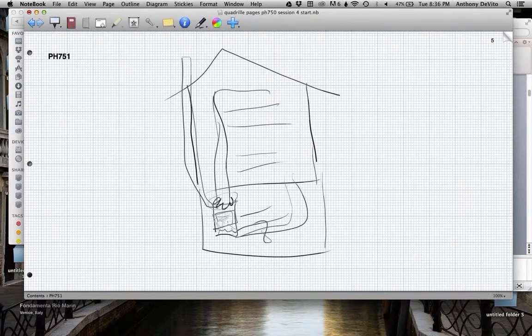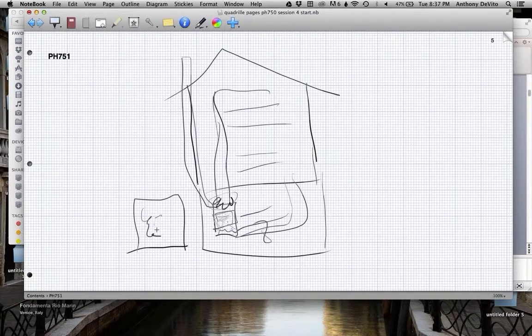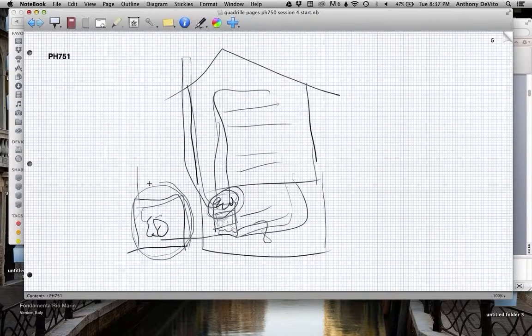So that's a bit bigger since you're doing the whole house, and the compressor is going to be noisy and large. So what they do is outside of the house, they put the compressor and the condensing coil outside of the house, and you've seen these outside. And if they get clogged up with leaves, that doesn't work because you can't take the heat away from the condenser. You got to clean that coil outside of the house. So it works exactly the same way, except it's a split unit. The evaporative coil is indoors, and the condensing coil and the compressor are outdoors.